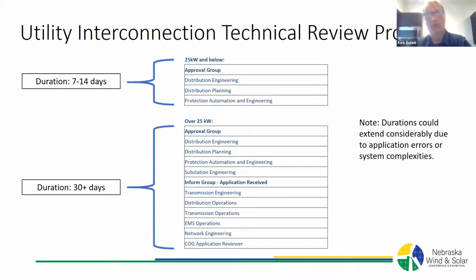When you get to the larger systems, which are often commercial, the number of groups really opens up. You have to start looking at substations, at the transmission in the area, and get transmission and distribution operations personnel involved, since they actually do the live switching of circuits on the grid. Then there's telemetry and communications, so the utility can see what that system is generating and not have it masked by the load, which is key for distribution and transmission planning going forward.